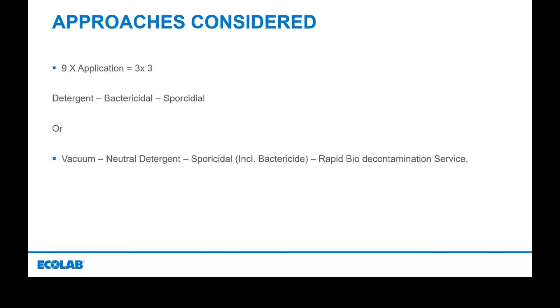Moving into the proposal in more detail: a vacuum clean to remove any physical dirt from the area before moving on to a neutral detergent application, with mechanical action involved through the use of a clean wipe. All soiling is removed, and it may have to be repeated so that all visual residues are removed - as would be the case at most sites.